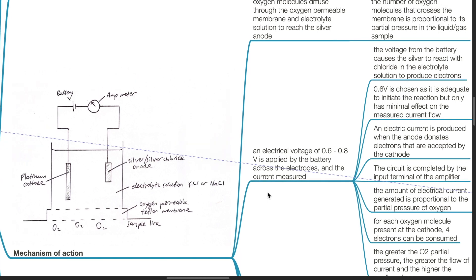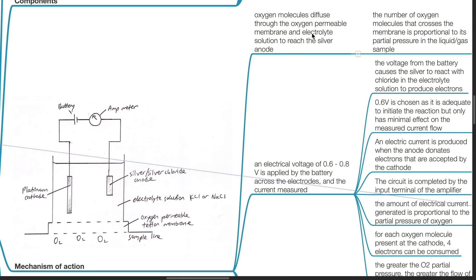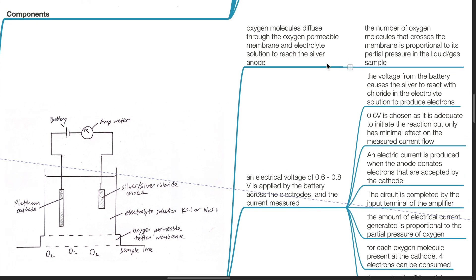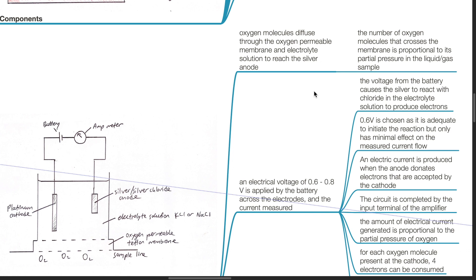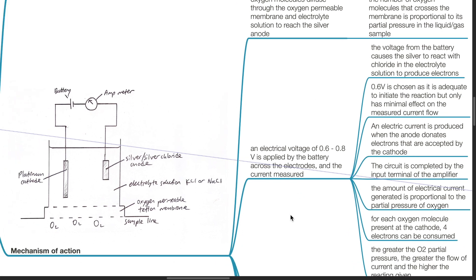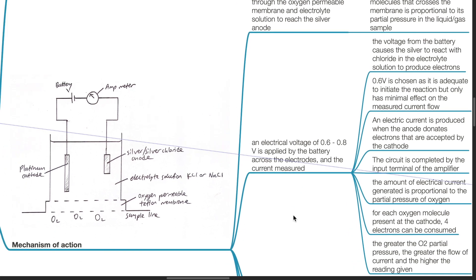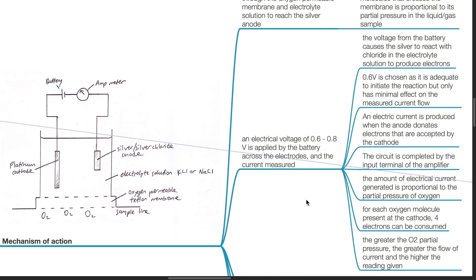Mechanism of action: Oxygen molecules diffuse through the oxygen-permeable membrane and electrolyte solution to reach the silver anode. The number of oxygen molecules that cross the membrane is proportional to its partial pressure in the liquid or gas sample. An electrical voltage of 0.6 to 0.8 volts is applied by the battery across the electrodes and the current is measured. The voltage causes the silver to react with chloride in the electrolyte solution to produce electrons. 0.6 volts is chosen as it is adequate to initiate the reaction but has only minimal effect on the measured current flow.